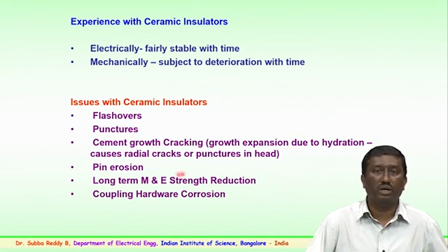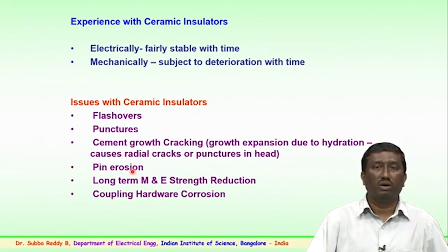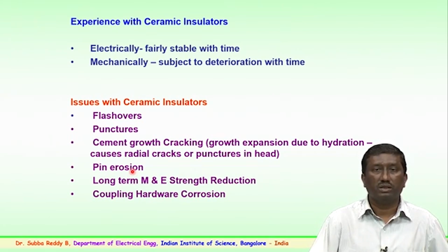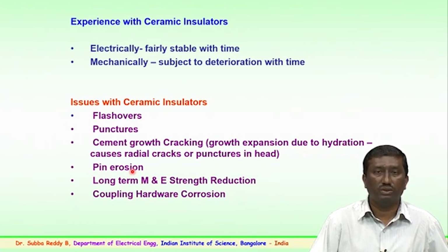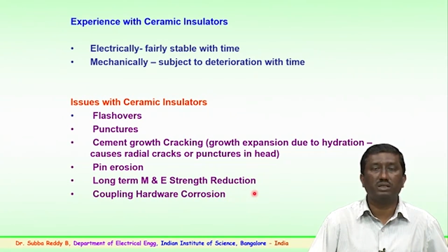Then pin corrosion: depending upon climate or environmental factors, corrosion on the pin has been noticed over a period of time. This could also lead to failure of insulators. Long term mechanical and electrical strength reduction takes place because of these issues.